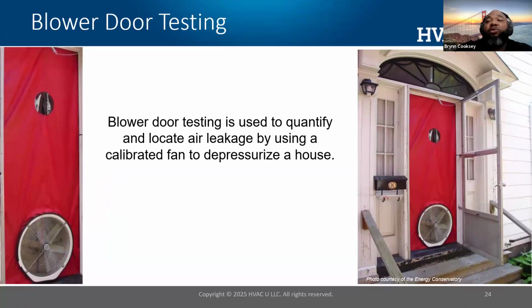Right? For best results, for the load calculation, you should conduct a blower door test. The blower door is a diagnostic tool that is going to pressurize or depressurize the house. Its goal is to try to quantify the building air leakage. This is important in a couple of different ways. Number one, if I know my building air leakage, I can refine my load calc. I can make it that much more accurate. Number two, even if my heat pump is sized accordingly, if I have a building shell problem, that customer might experience discomfort in certain areas because of building leaks. And if I'm able to detect those, I can include that work in my work scope just to ensure that my customers are comfortable. So it's pretty important to run a blower door test.